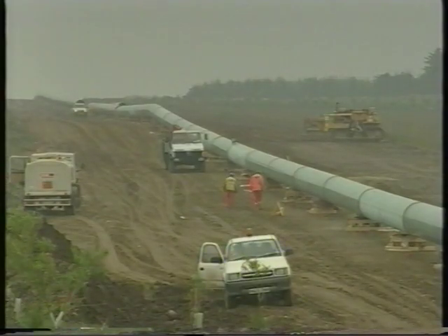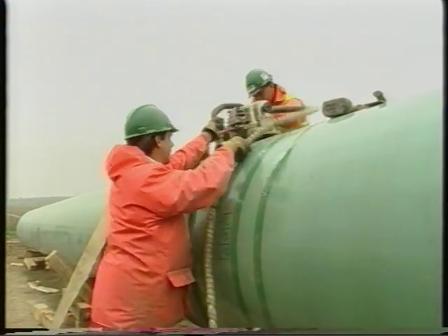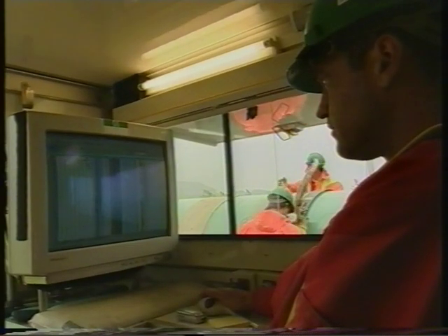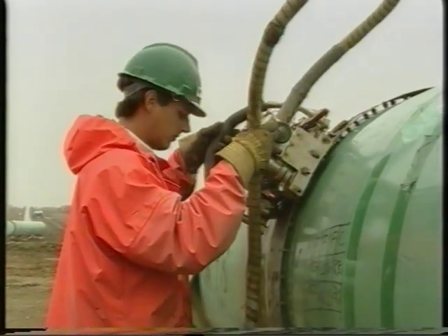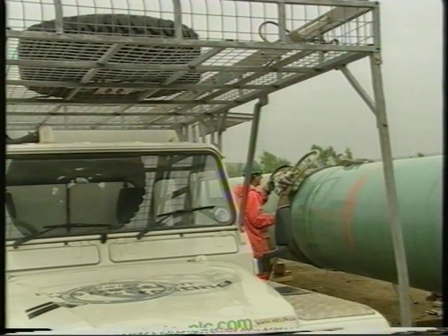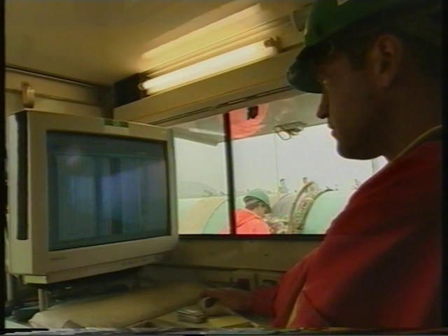The films were checked at the site compound for welding defects. Any areas of concern or defects were highlighted for investigation and repaired on site. On this project, additional inspection by automatic ultrasonic testing was carried out back-to-back with X-ray testing to assess its use as a safer alternative. Immediately behind the front welding operations, the welds were checked by fixing the UT machine to the same band that the welding machines were fixed to, thus enabling the machine to rotate around the welded joint.